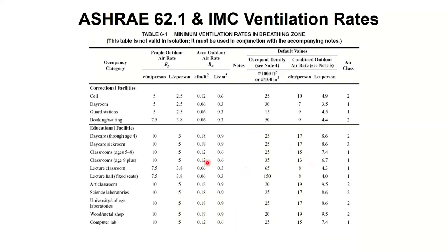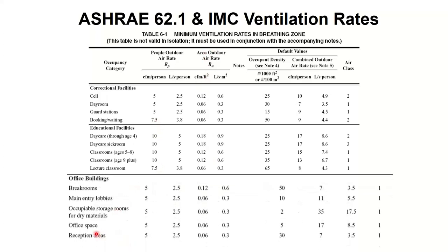So now when you look it up, this is one of like four or five pages in the ASHRAE handbook. When you look it up, ignore the liters per second. I don't care about that. Look at the CFM. So I need to take the CFM per person and the CFM per square foot and add the two of them together. So if I look at the office building example we were just talking about, it's 5 CFM per person plus 0.06 CFM per square foot. And for an average density of space, that's around 17.